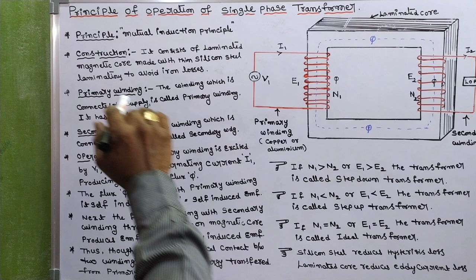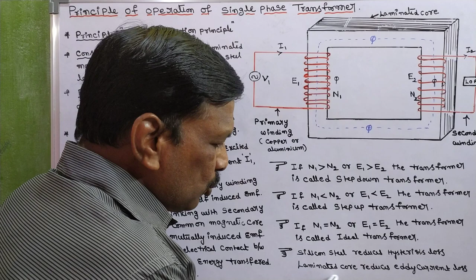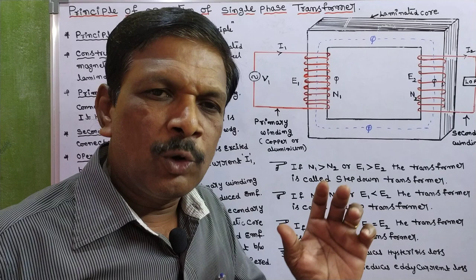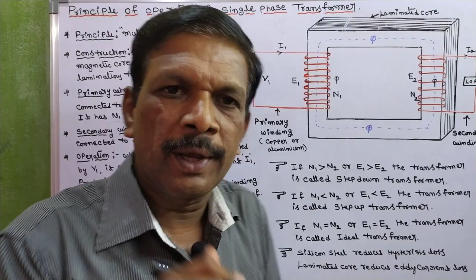Coming to construction: this is the basic transformer diagram. It has a laminated magnetic core made with thin silicon steel laminations. Why do we use silicon steel, and why laminated core? When we use silicon steel, it reduces hysteresis loss. When we use laminated core, it reduces eddy current loss. So when we use laminated silicon steel core, the iron losses are reduced. That's why in any transformer, the core is made with silicon steel laminations.